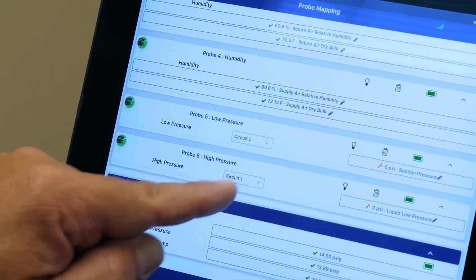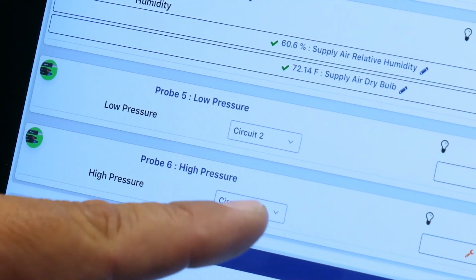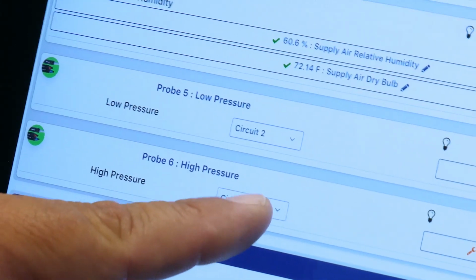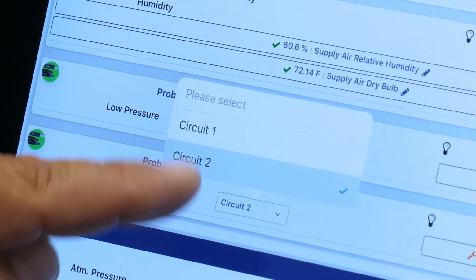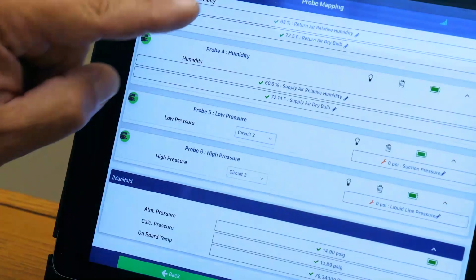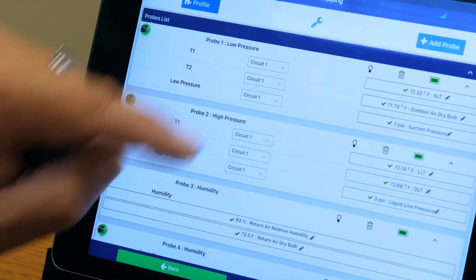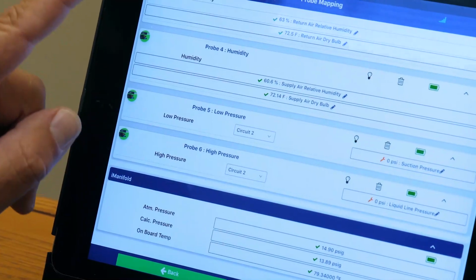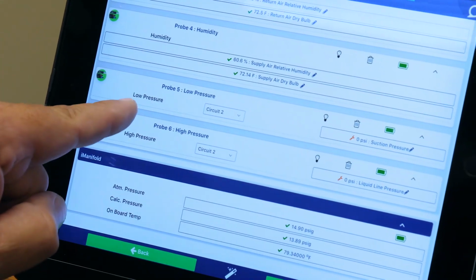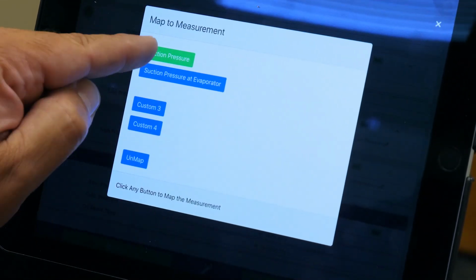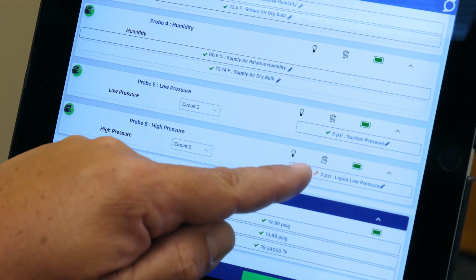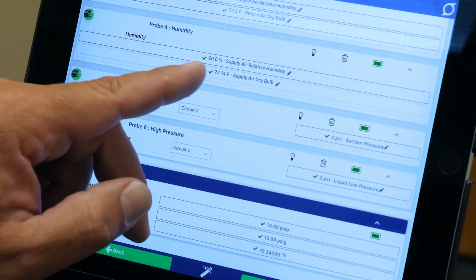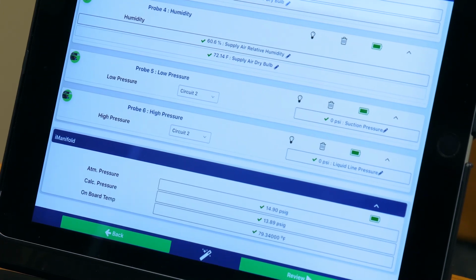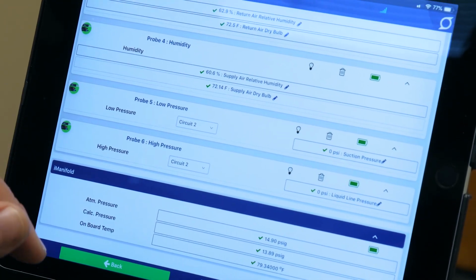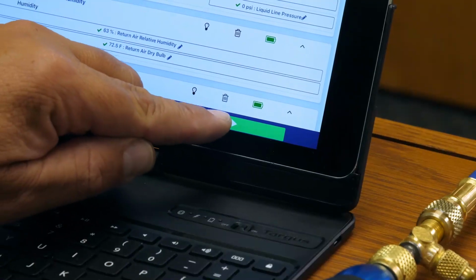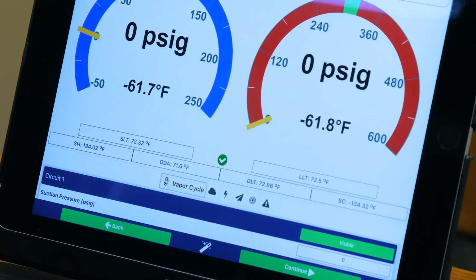So going right back down to our high pressure, very simple to fix. That is our circuit number 2. We're going to tap circuit 1, select circuit 2, and we're all set. Going down the line over here, everything's set. Our wrench is green. Let's verify those probes to make sure we don't have to do this again. That's our low pressure side, suction pressure. Same thing with the high side, high pressure. Now, of course, adding in your secondary liquid line and suction line temperatures, that's going to apply the same thing as in the beginning. Once everything's set, simply tap review, and we're ready to work.